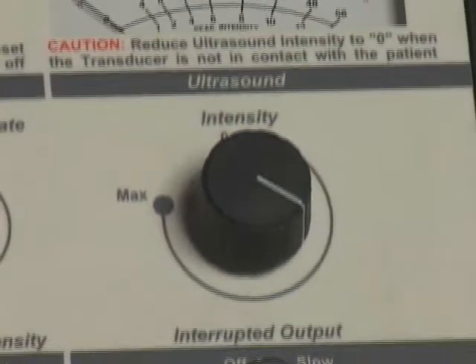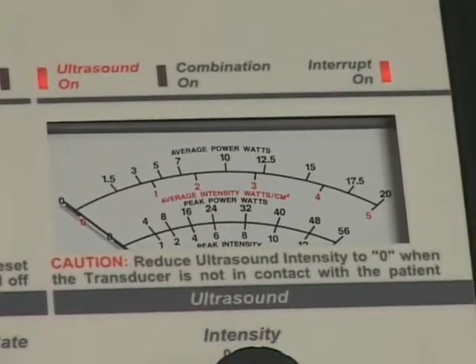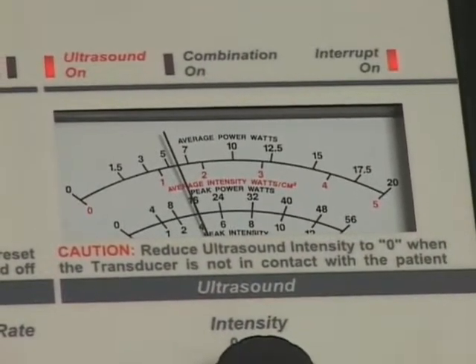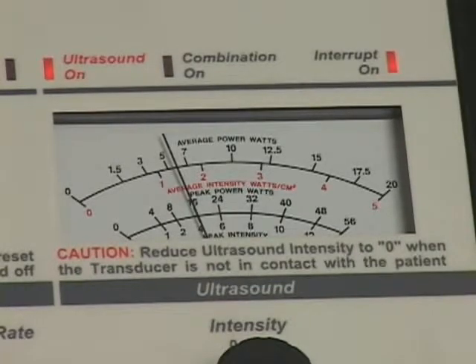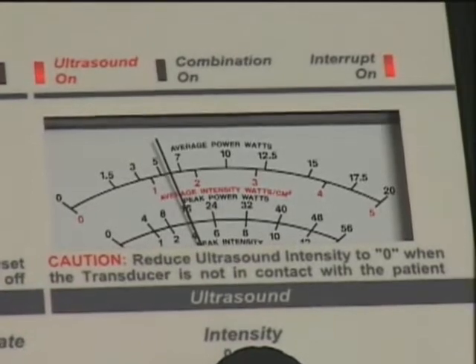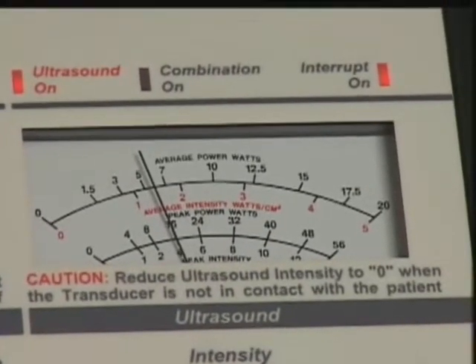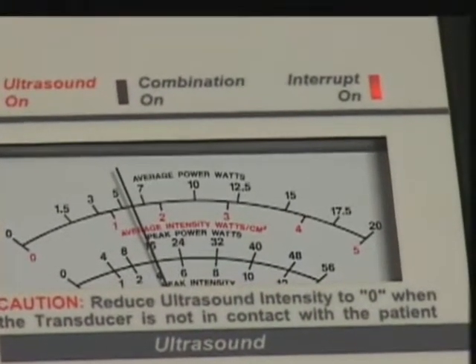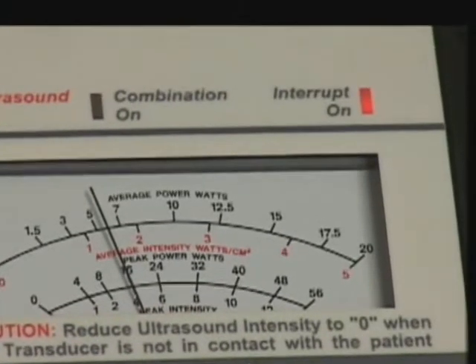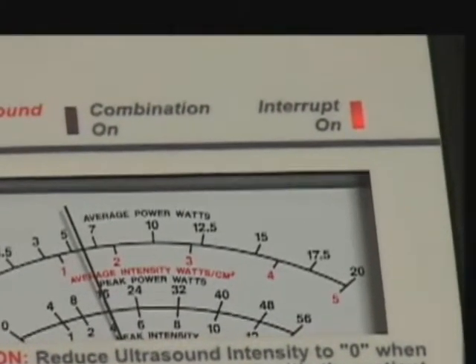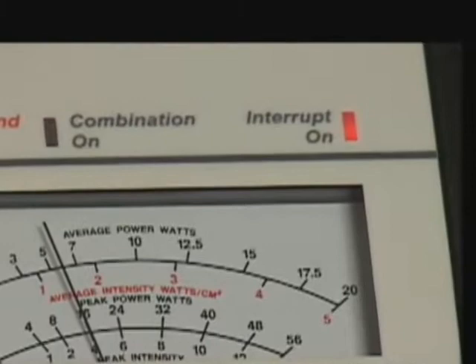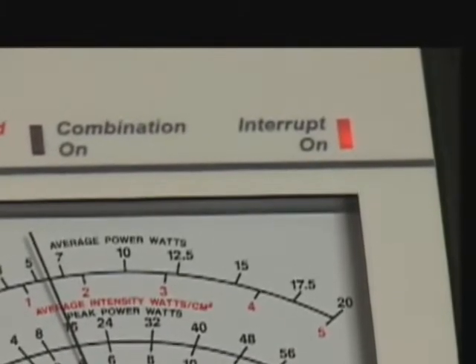If desired, adjust the ultrasound interrupted output control now. When the ultrasound interrupted output control is rotated clockwise, enabling an audible click, the interrupt on indicator light, located above the upper right corner of the ultrasound meter, will illuminate, and the ultrasound meter indicator will rise and fall, indicating interrupted cycles, provided the transducer is not in the ultrasound cradle.